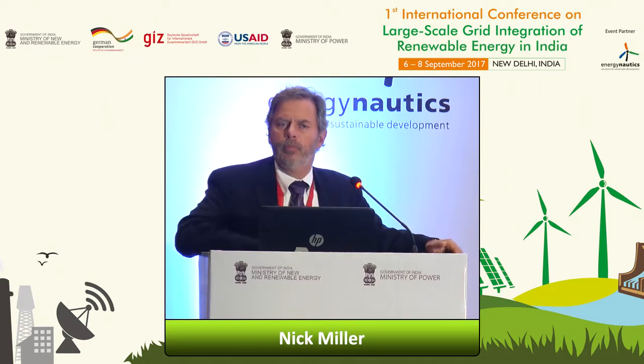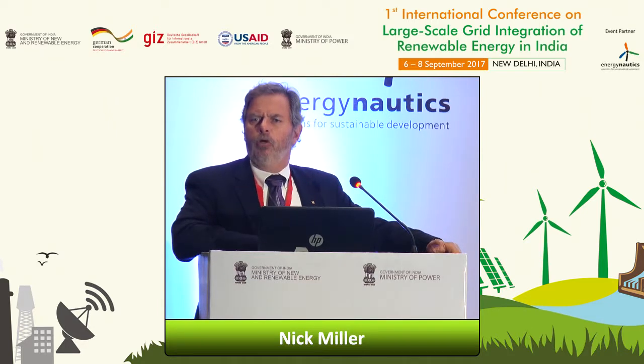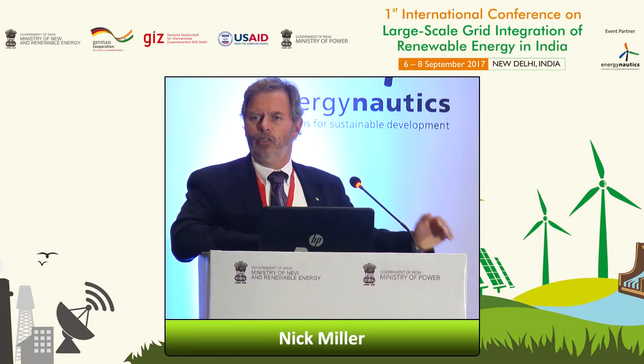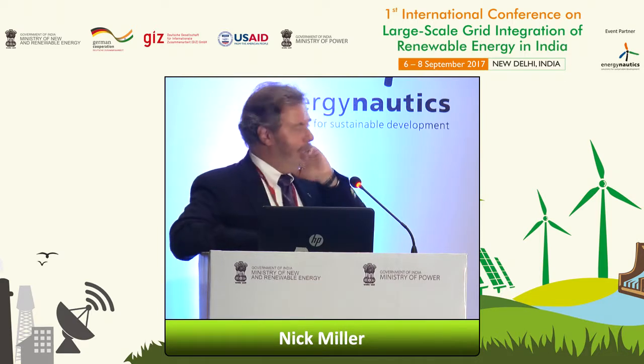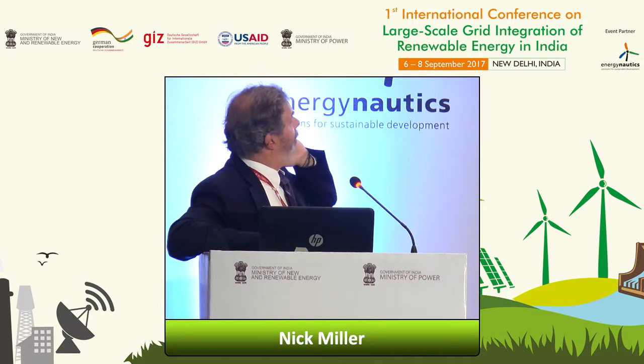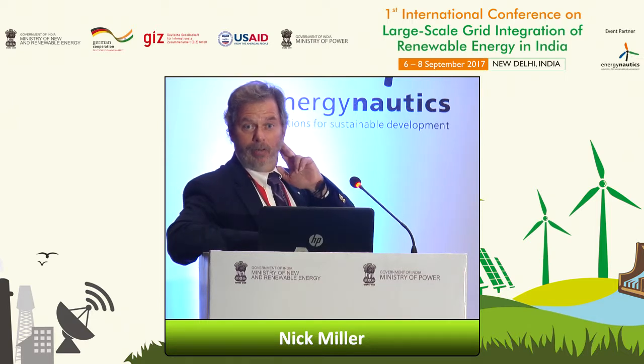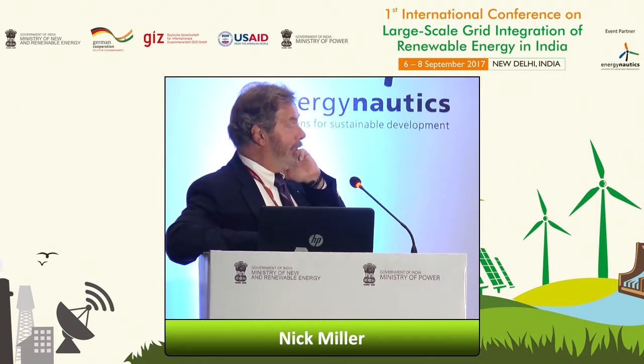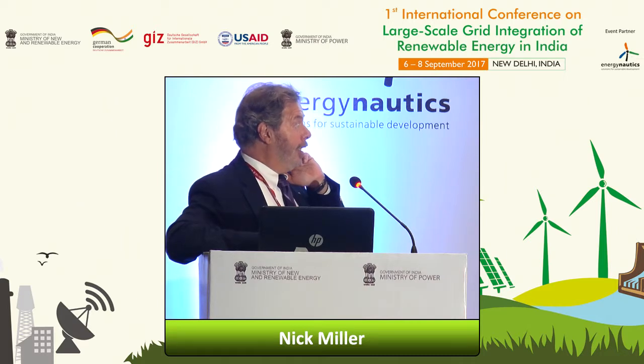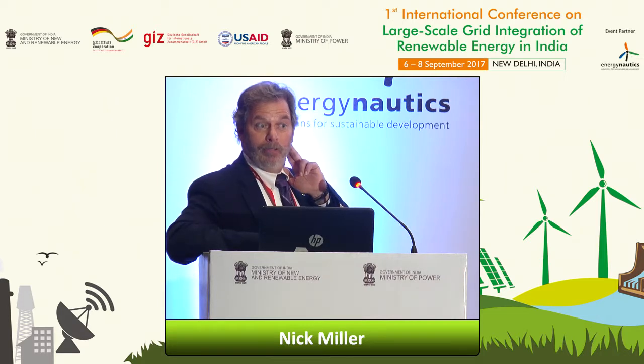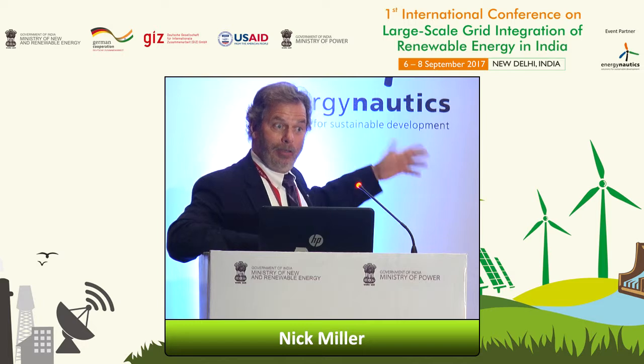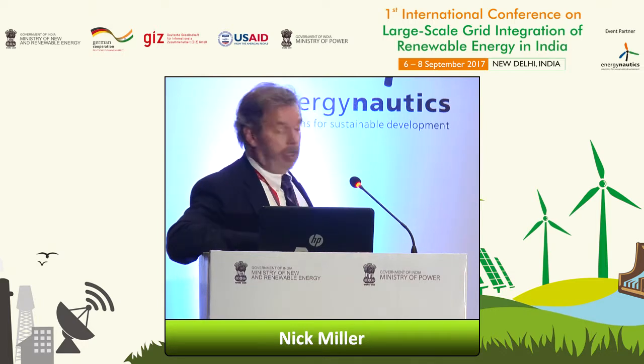But there are some things, like thou shalt go forth and test the plant. Well, Mother Nature isn't terribly cooperative sometimes, and sometimes the grid people aren't very cooperative either. So the first thing you've got to do is make sure you have a substantial amount of wind, and it's better if it's pretty steady, because if the wind is moving all around, you have active power variations that cloud your results. You've got to be careful.